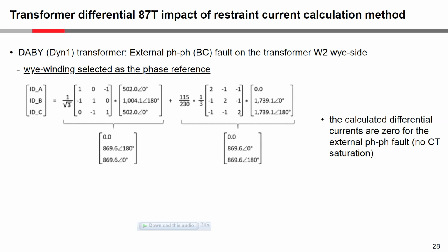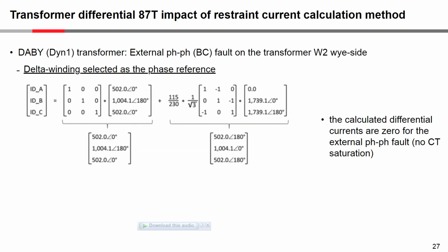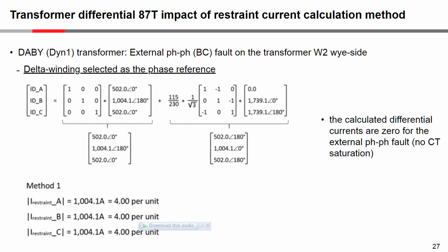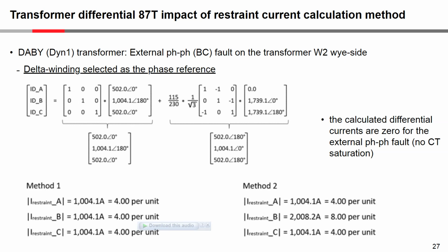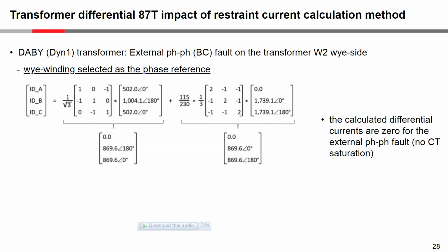Now, what we have here is exactly the same fault, exactly the same current. If you look at the winding 1 and winding 2 side measured currents, they're exactly the same. All we've done differently is select the Y winding as the phase reference. But again, because it's a delta-Y transformer, the matrix used on the Y side needs to have the zero sequence subtraction, and then we have the requisite matrix on the delta side. And again, it's an external fault, and if you sum the compensated currents for each phase, you will see that the calculated differential current would be 0.